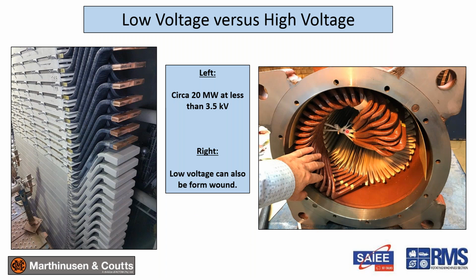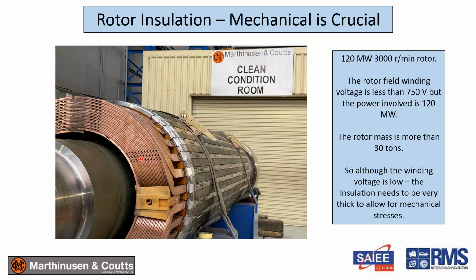And low voltage doesn't have to only be mush wound with round copper. It can also be form wound. This is a 120 megawatt rotor. Rotor voltage less than 750 volts, but massive insulation considerations to be taken into account for the mechanical considerations. I mean, if you base the insulation thickness on the voltage, it would be sort of 1 millimeter thick, and yet it's way more than that for mechanical considerations.